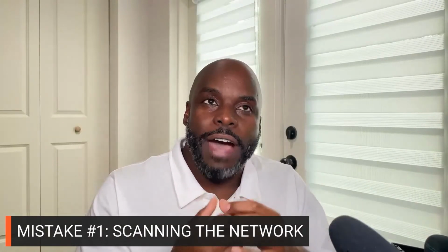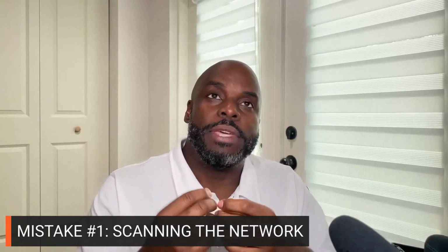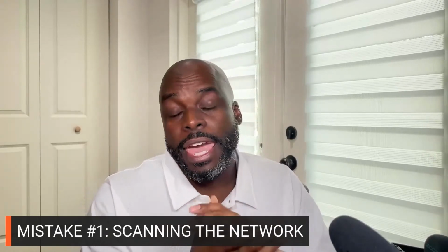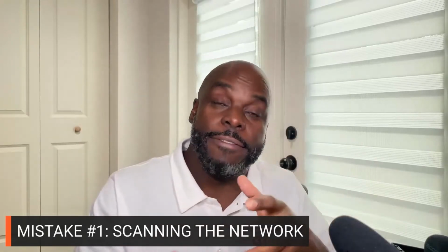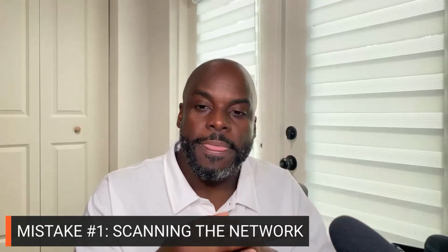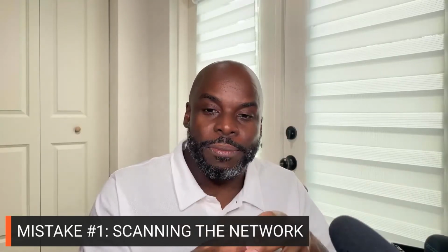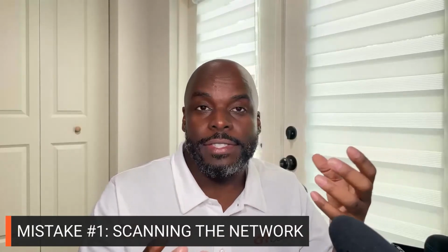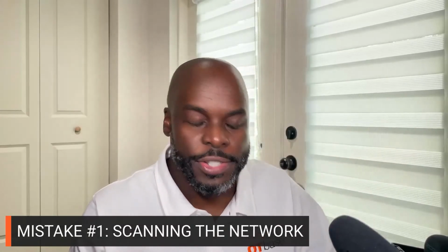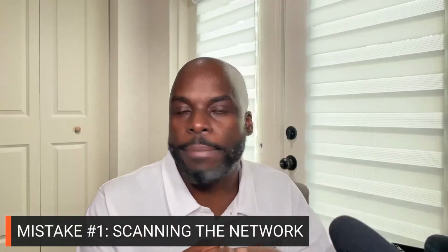The problem with IT scanners isn't that they're active, it is that they are foreign. They speak an entirely different language that the device just doesn't understand. And they do it at a volume and pace that these OT devices just can't handle. Just the influx of scanning overwhelms a PLC.